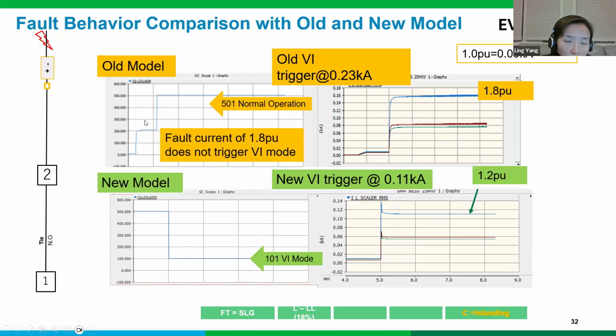Before we adjusted the parameters, under this circumstance the inverter may not sense there's a fault in the system and remains in normal operation, but it could potentially push its output to 1.8 per unit of its normal rating. By adjusting the threshold of the virtual impedance mode, under the same location and same fault, the inverter is able to sense the fault in the system and goes into the virtual impedance mode.